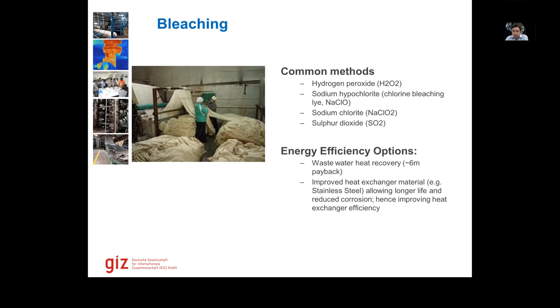Then we can also improve the heat exchanger material inside. For example, if we have mild steel or other ferrous materials, we can consider switching to stainless steel, which provides quicker heat exchange and has longer life. It also reduces corrosion and improves heat exchanger efficiency. One issue we often see is that heat exchangers in these machines are leaking, where we have too high or too low pH, or clogging also takes place. Stainless steel heat exchangers provide a lot of protection against that, so a lot of maintenance cost also reduces here.